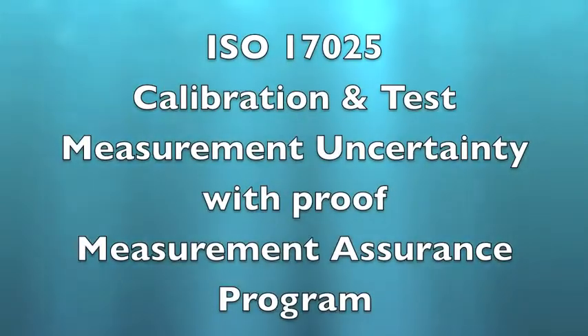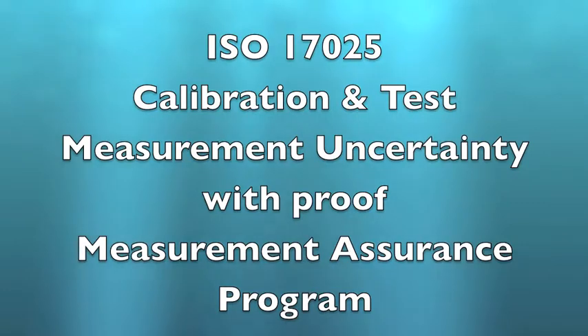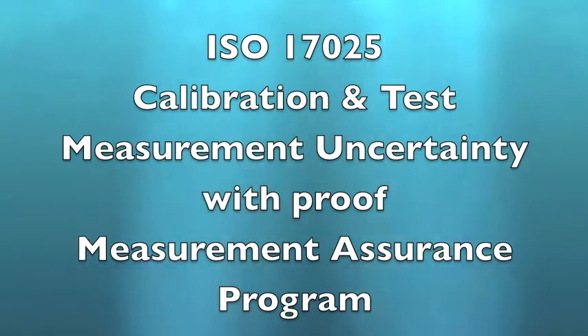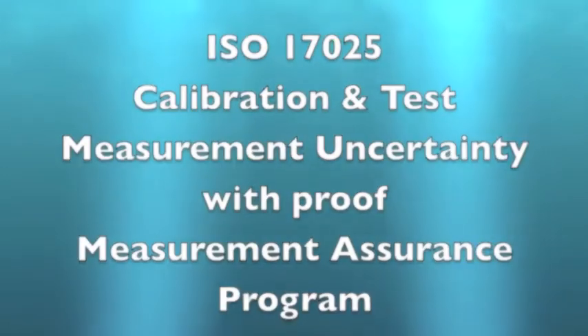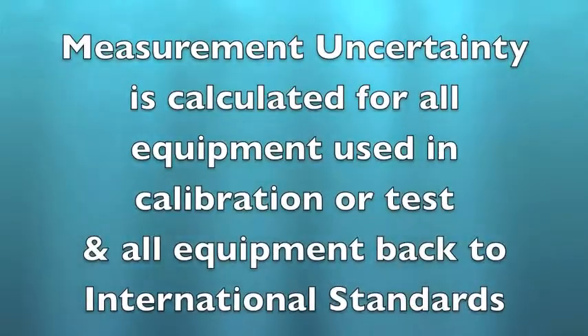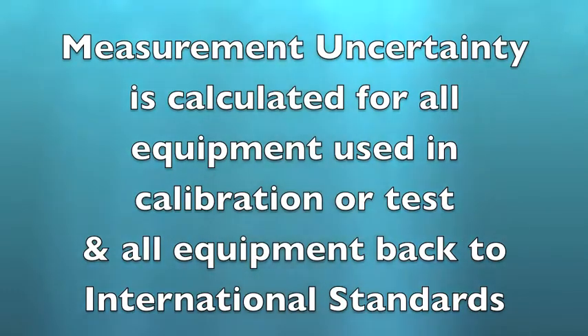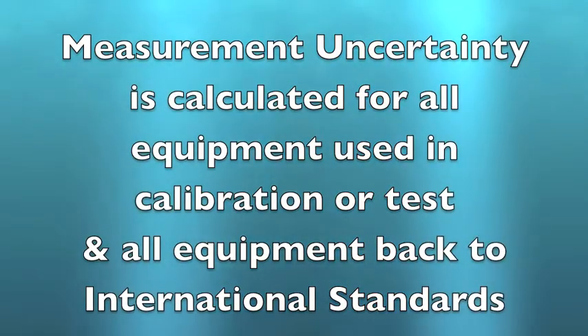In the laboratory, ISO 17025 concentrates on calibration and test, the measurement uncertainty with all the proof, including calculations, as well as a measurement assurance program for all the types of measurements made by the laboratory. Measurement uncertainty is calculated for all the equipment used in the calibration or the test, and all the equipment used to calibrate that equipment, all the way back to the International Standards for Measurements.